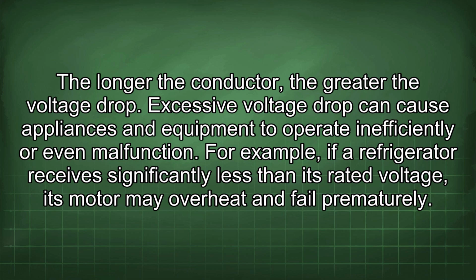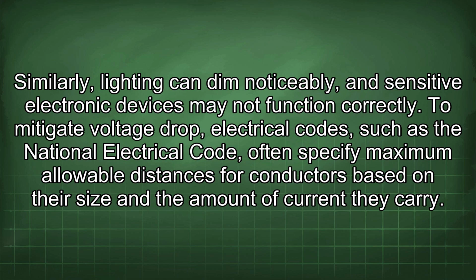Excessive voltage drop can cause appliances and equipment to operate inefficiently or even malfunction. For example, if a refrigerator receives significantly less than its rated voltage, its motor may overheat and fail prematurely. Similarly, lighting can dim noticeably, and sensitive electronic devices may not function correctly. To mitigate voltage drop, electrical codes, such as the National Electrical Code, often specify maximum allowable distances for conductors based on their size and the amount of current they carry.